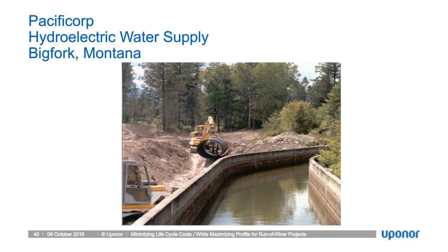You'll see from this picture here, water supply to the turbines was divided between a concrete-lined open channel and a buried wooden stave pipe. In this photo, the old wooden stave line was to the left of the concrete channel. The same alignment was selected for the replacement of the Weholite pipe.